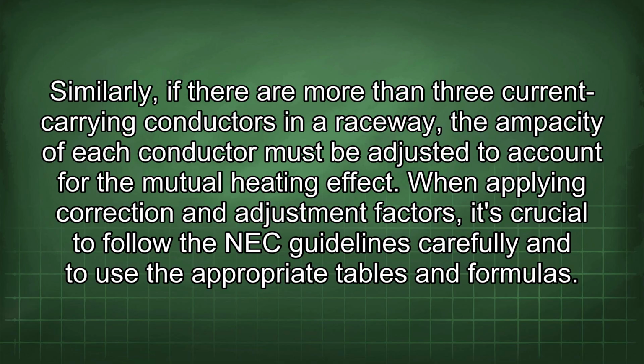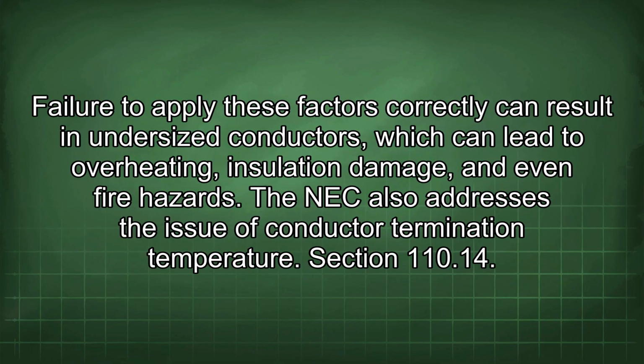Similarly, if there are more than 3 current carrying conductors in a raceway, the ampacity of each conductor must be adjusted to account for the mutual heating effect. When applying correction and adjustment factors, it's crucial to follow the NEC guidelines carefully and to use the appropriate tables and formulas. Failure to apply these factors correctly can result in undersized conductors, which can lead to overheating, insulation damage, and even fire hazards. The NEC also addresses the issue of conductor termination temperature.